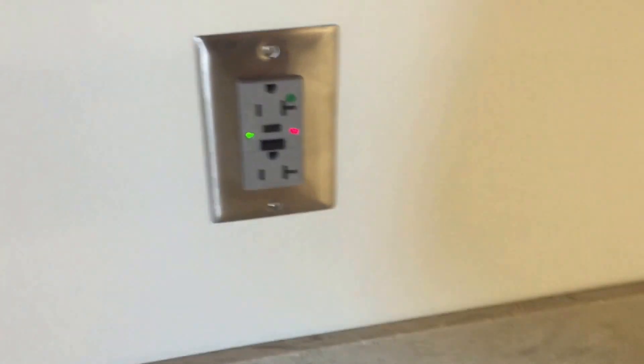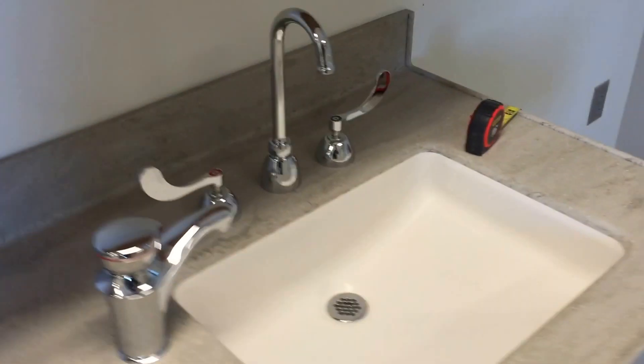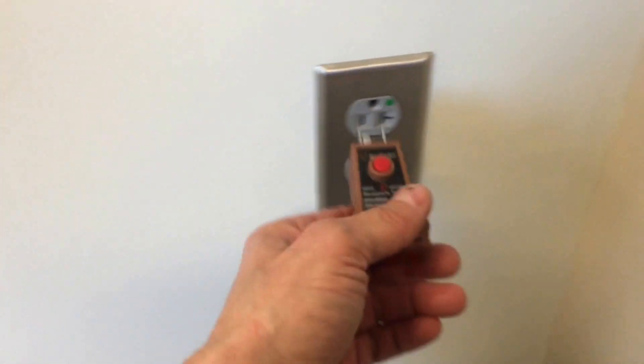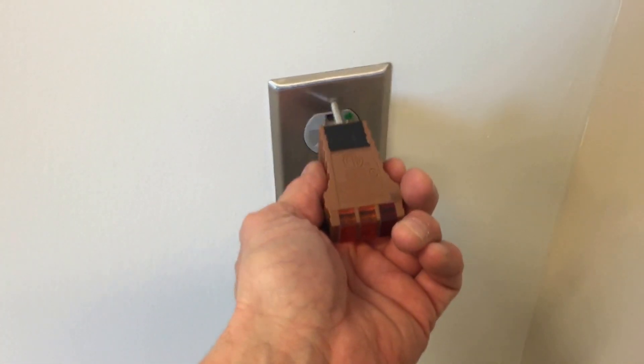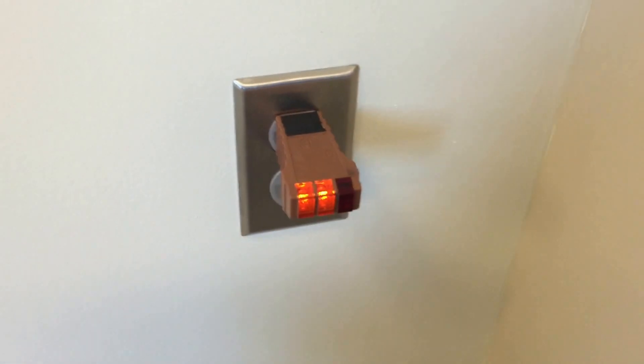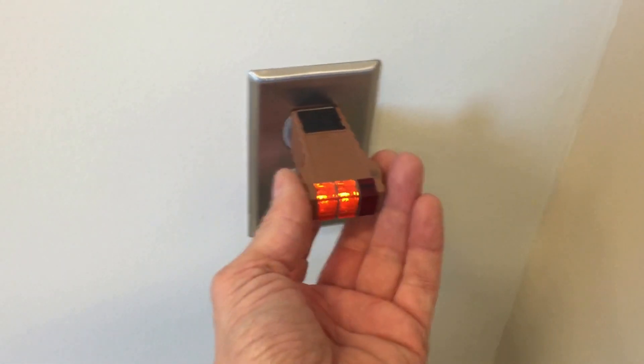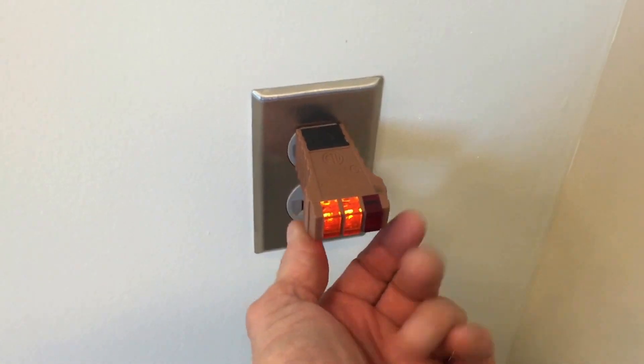Now the reason I did that was to show you that this receptacle over here is not GFCI protected. I'm going to plug my tester in so the receptacle has power. When I push the test button, nothing happens. The plug remains energized. It should trip.